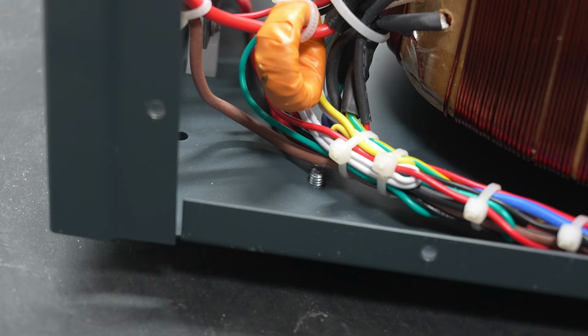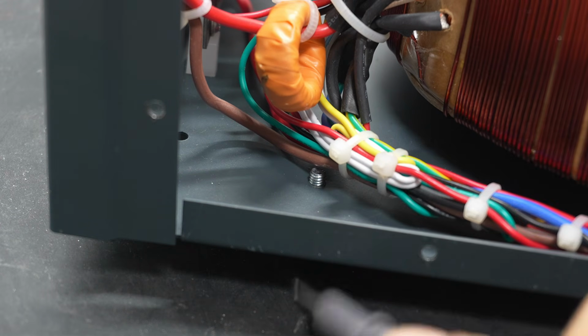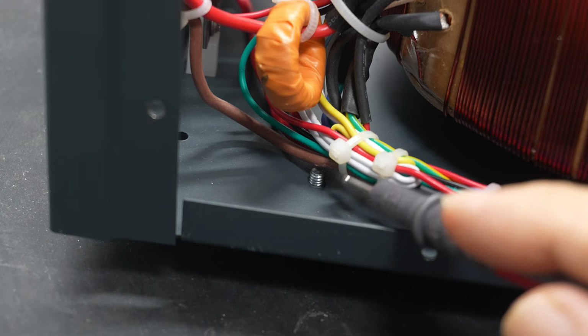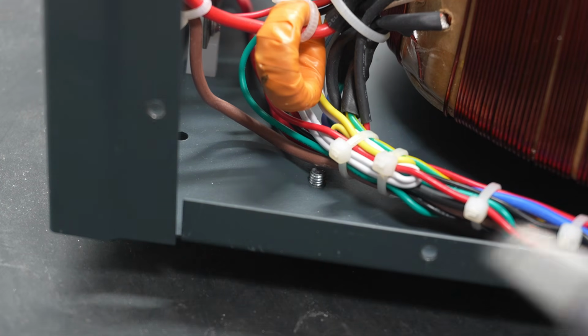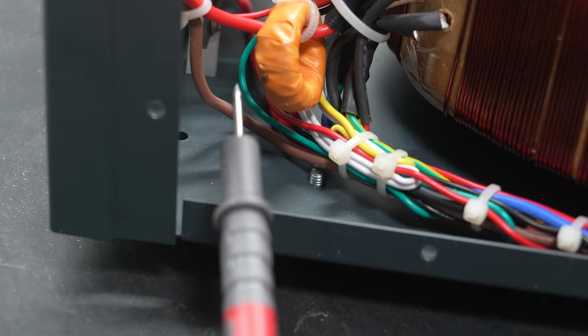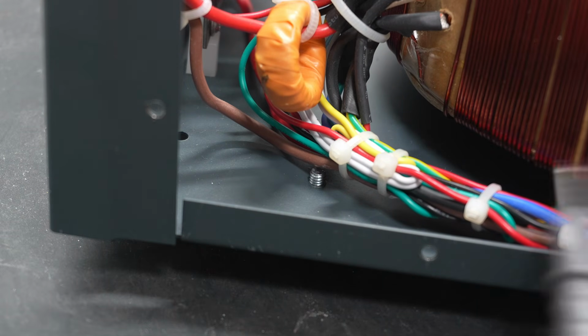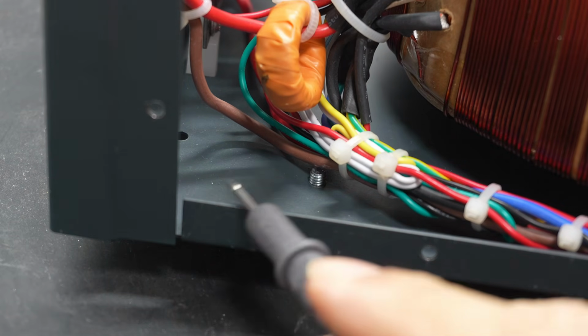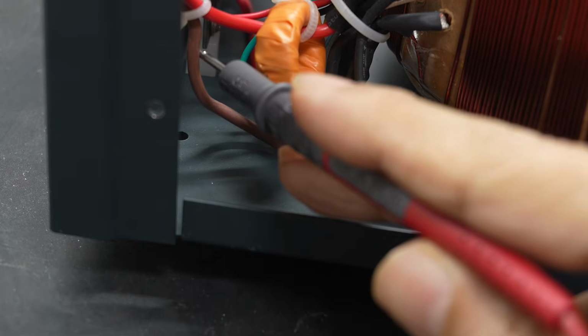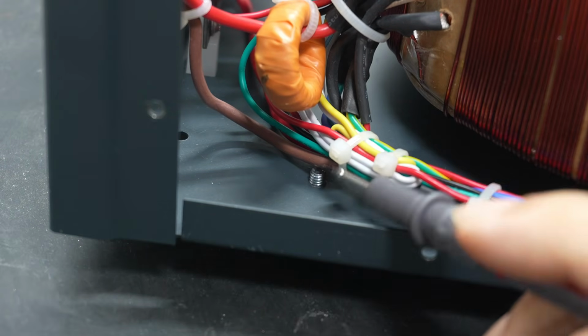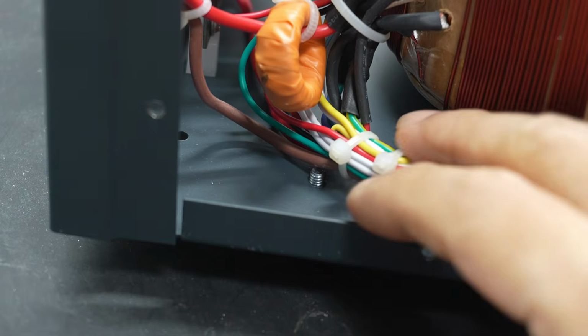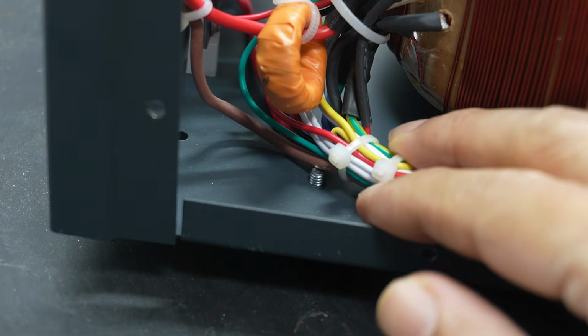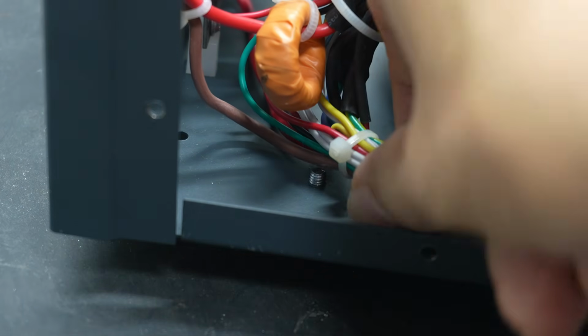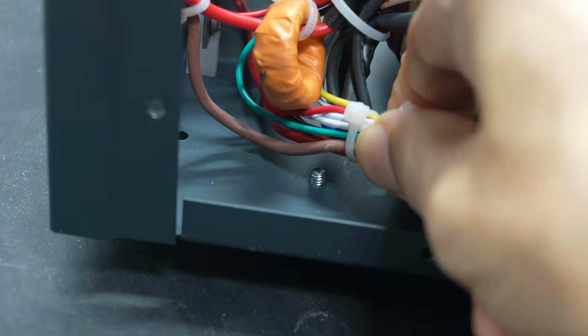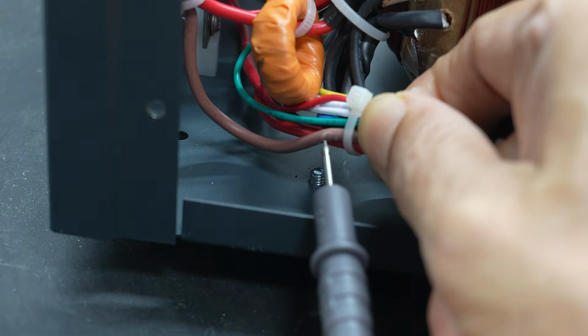As I've been probing around in the box, I came across this little screw here, one of the feet, that's come through here. As you can see, it was actually rubbing on the wire — this is the live wire, it comes through here and goes up to the switch. Now this wire is on this screw, not loving that — a bit of vibration over time could cut through that plastic. If I rotate this around, you can already see some rubbing marks on the wire.